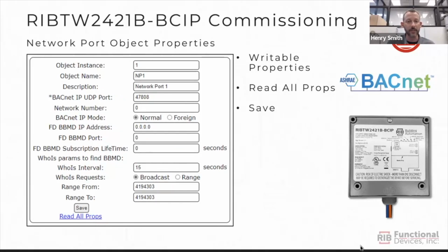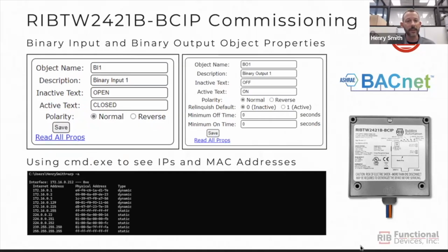Again, anything that's writable has a text box where you can do your configuration here, changing the description or the name or whichever port you might want to use for the product. And again, the button at the bottom to read the other read-only properties and to save any configuration settings that you've changed. And the last two objects this device has, so one being the device object, two the network port object. You also have the binary input and the binary output.